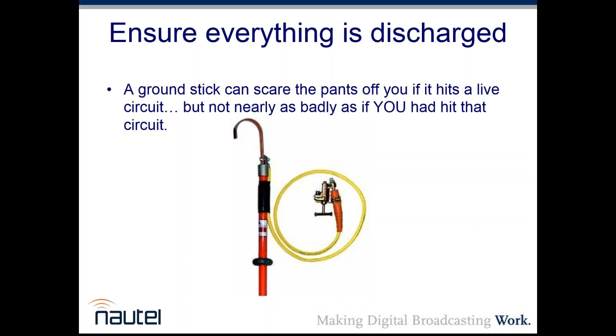But the other thing about a ground stick, if you don't have one, and a lot of modern transmitters where they don't have openly accessible voltage and where they run at lower levels don't have built-in ground sticks, you can build one in a heartbeat for about $20. Just a broomstick, some duct tape, and a set of booster cables.